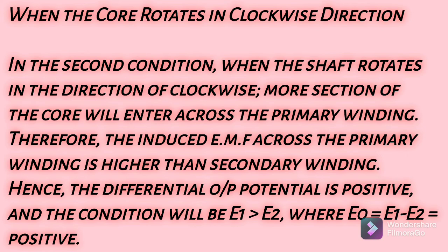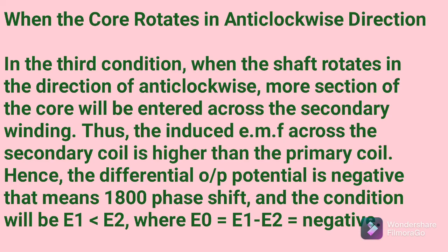Then the second case will be when the core rotates in clockwise direction. In the second condition, when the shaft rotates in the direction of clockwise, more section of the core will enter across the secondary winding across the primary winding. Therefore the induced EMF across the primary winding is higher than the secondary winding. Hence the differential output potential is positive, and the condition will be E1 greater than E2 where E0 equals E1 minus E2 will be positive.